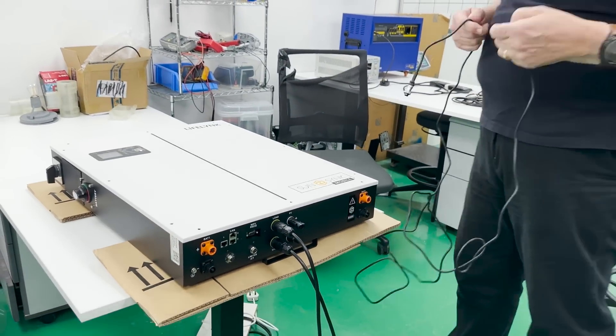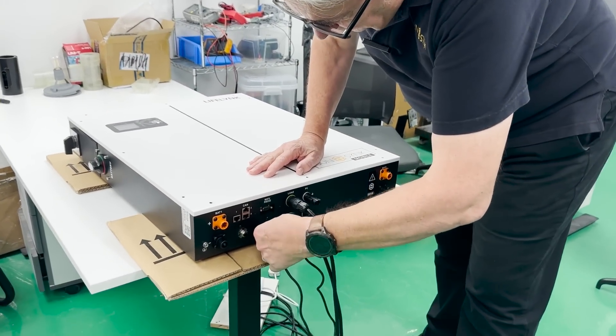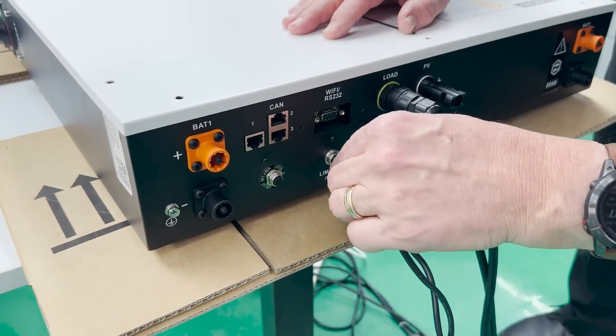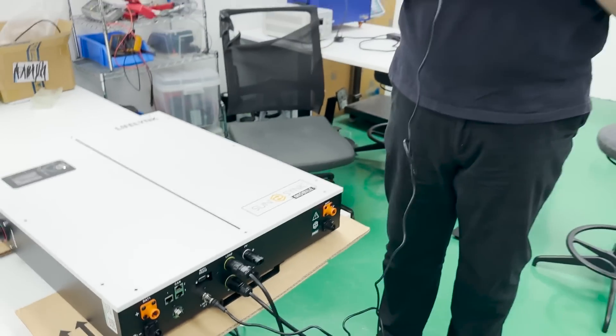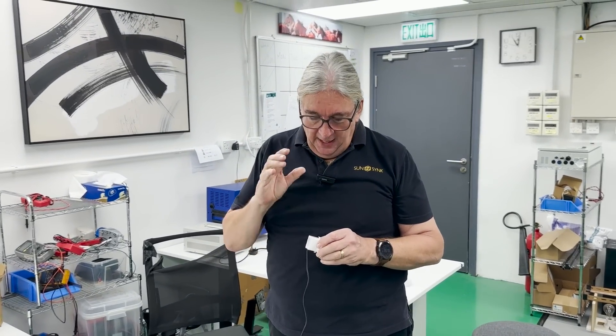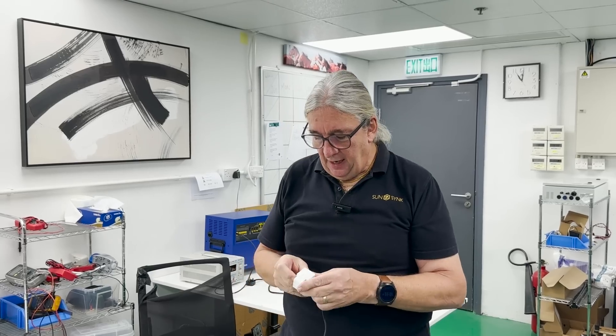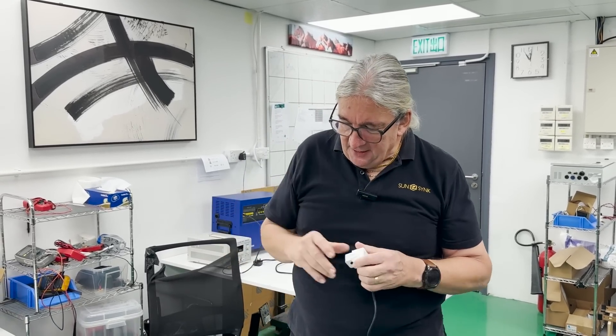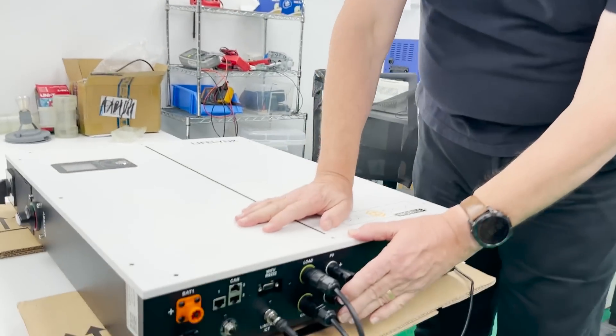The CT coil prevents export — it's marked as 'limiter.' I connect my CT coil in here — making sure the orientation is correct, it seals and locks in place. The CT coil clamps onto the incoming cable and that prevents or controls the export. Don't forget to note the arrows on the CT coil — the arrows face towards the unit.